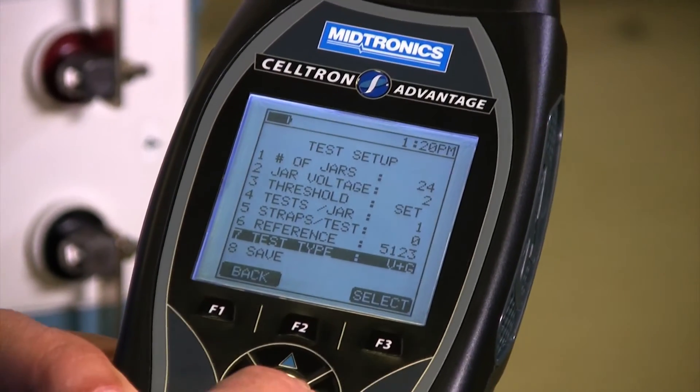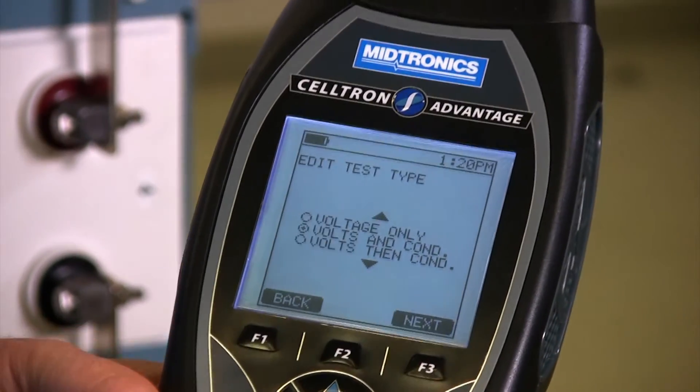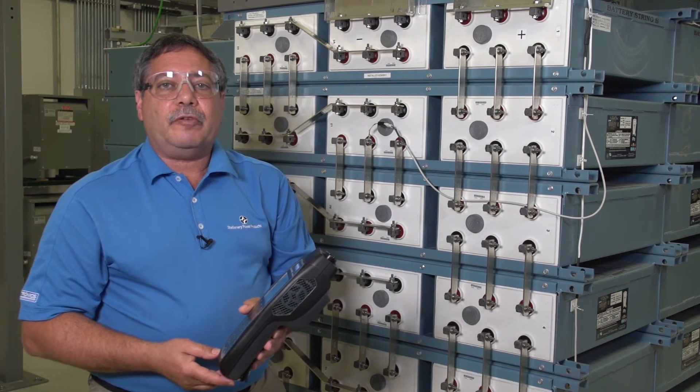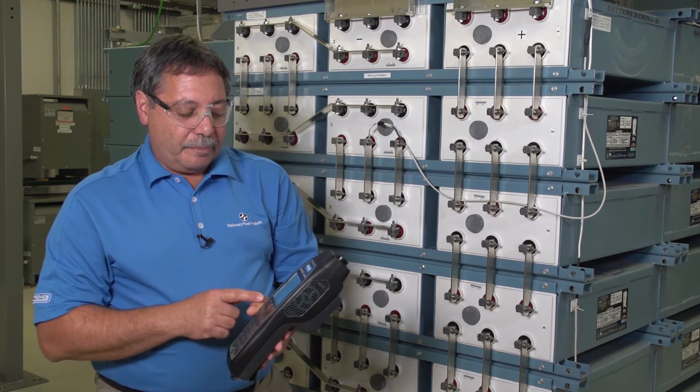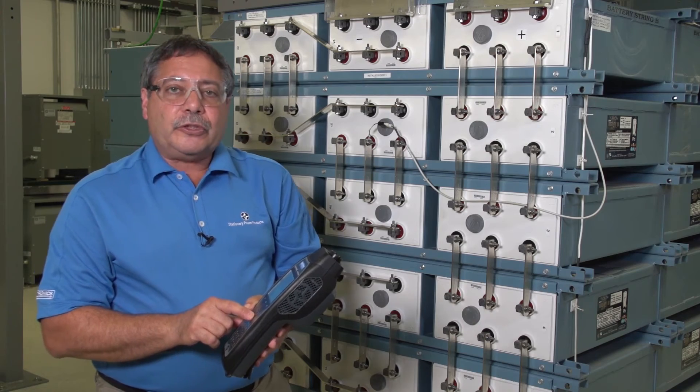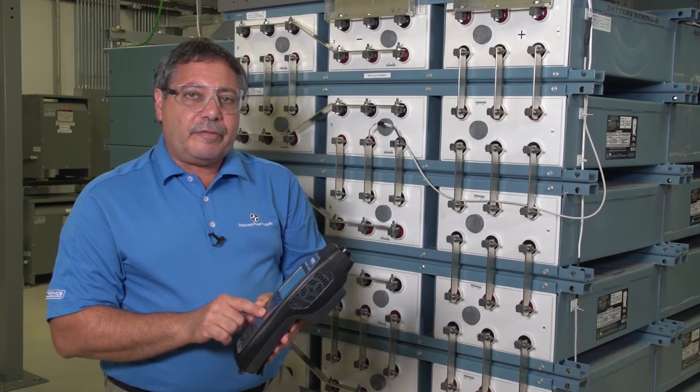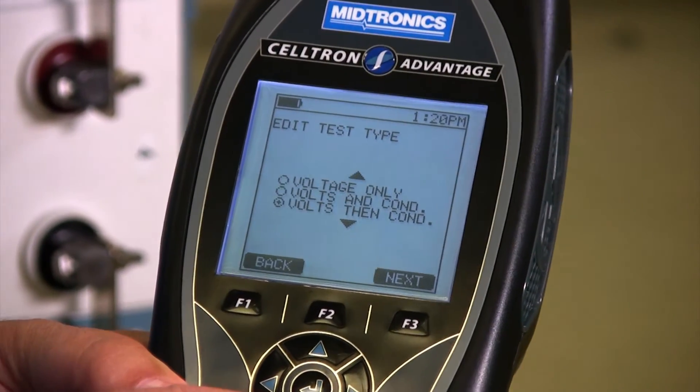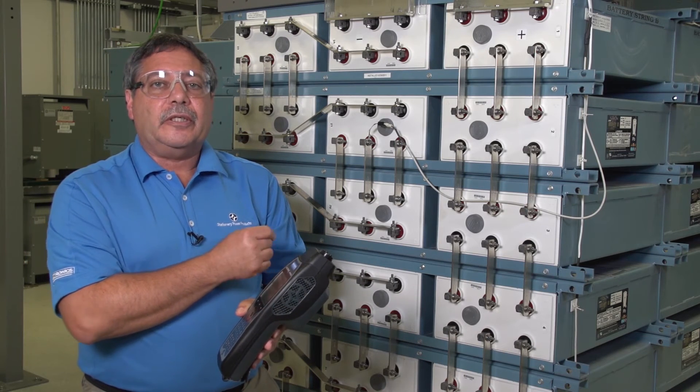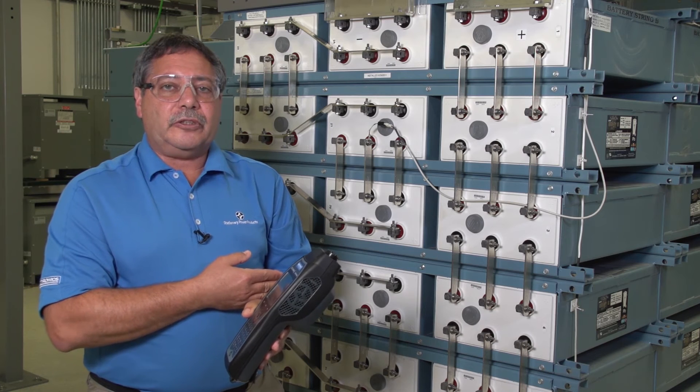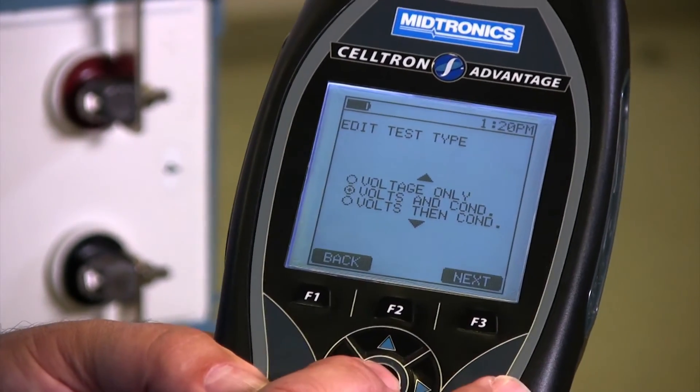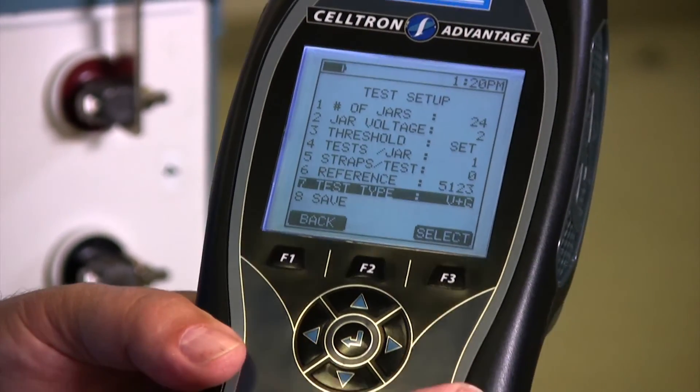Next is the test type. So test type gives me three options. If I happen to be doing volts only because maybe I have to check my voltages on a monthly basis, I can do that. Volts and conductance is the default where it takes the voltage readings and then does the conductance reading right after it. Or you have volts then conductance mode, which will let you take all the voltage readings first of all the cells, then go back and do the conductance readings and it puts the two readings together. So we're going to pick volts and conductance, which again is the default.